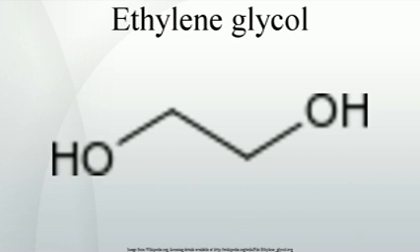Ethylene glycol disrupts hydrogen bonding when dissolved in water. Pure ethylene glycol freezes at about −12°C, but when mixed with water, the mixture does not readily crystallize, and therefore the freezing point of the mixture is depressed. Specifically, a mixture of 60% ethylene glycol and 40% water freezes at −45°C (−49°F). Diethylene glycol behaves similarly.